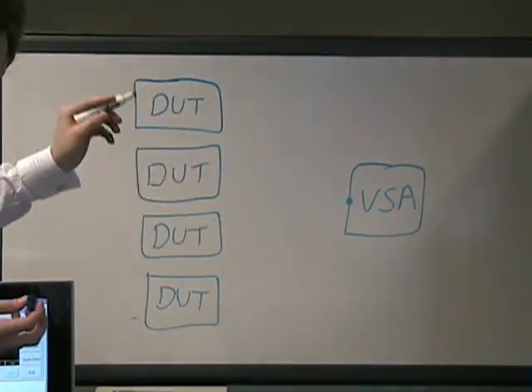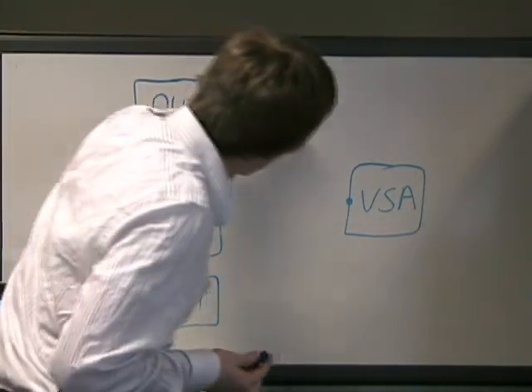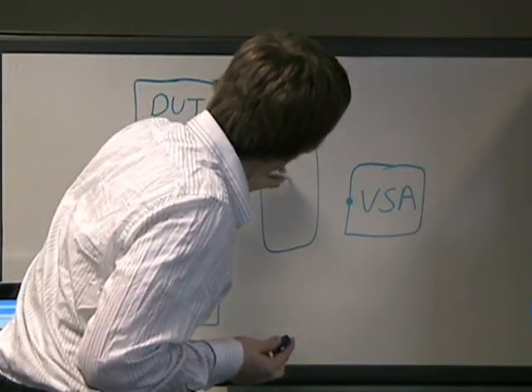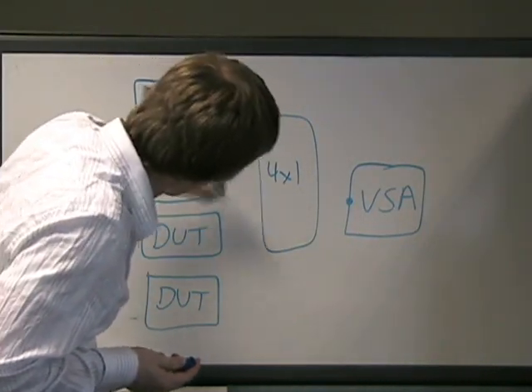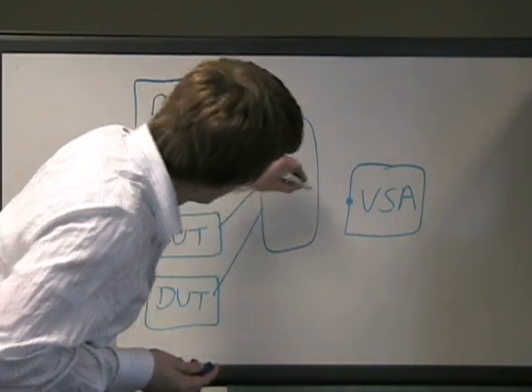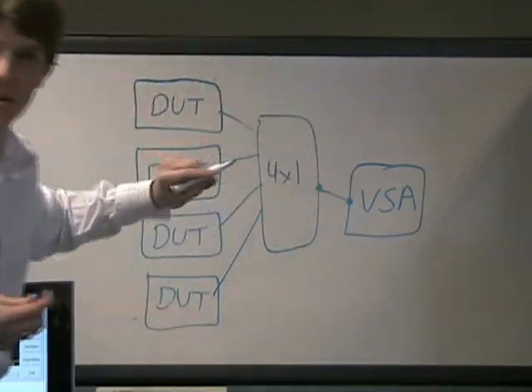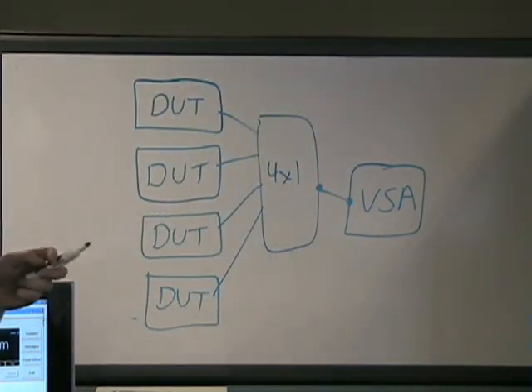So what I can do in this scenario is use switching or a multiplexer to connect each of these DUTs to my vector signal analyzer. You can see I can connect the different channels of the MUX and it'll simply measure the output at the COM port of the switch.